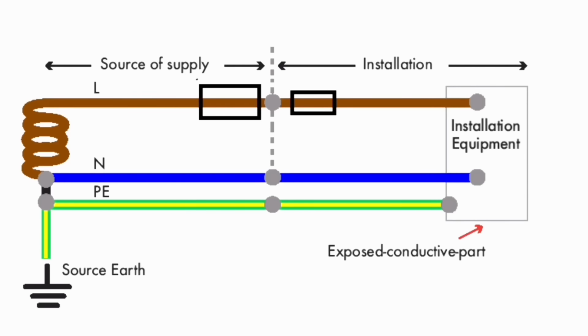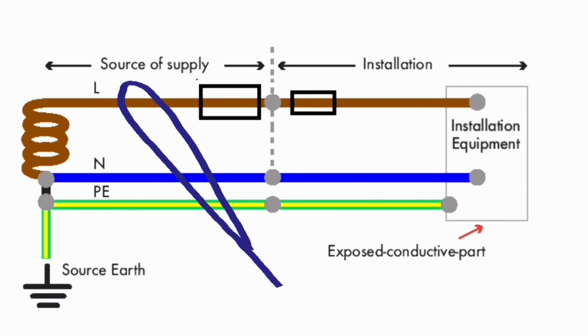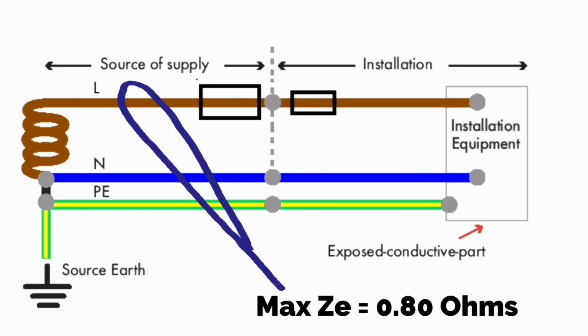The installation shown on the right hand side could be a lot shorter in length than the supply authority's cable, comprising of a line, a neutral and a CPC conductor within circuit. As with the supply authority side, we have a separate line, neutral and CPC in circuit. The fuse for this circuit will not be 100 amps, but considerably less, maybe 20 amps, and would be located within the distribution board itself. The maximum external earth fault loop impedance for a TNS earthing arrangement is 0.8 ohms.